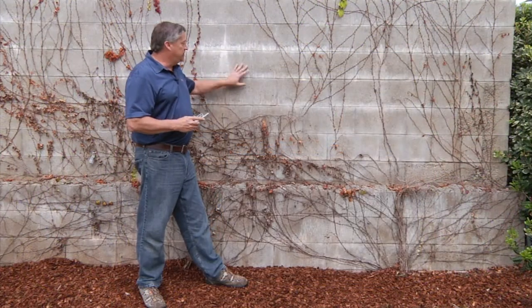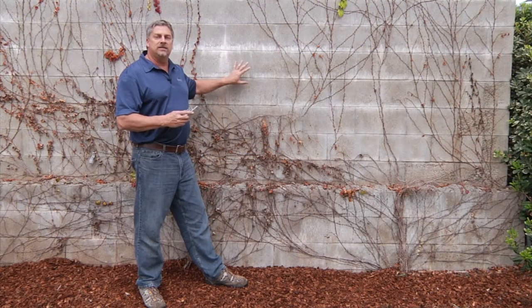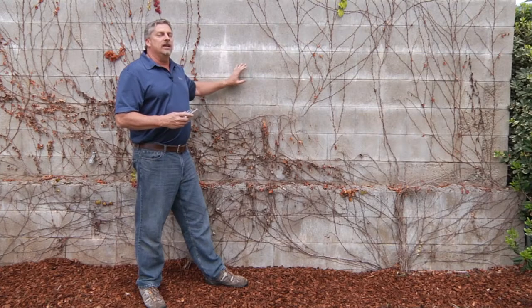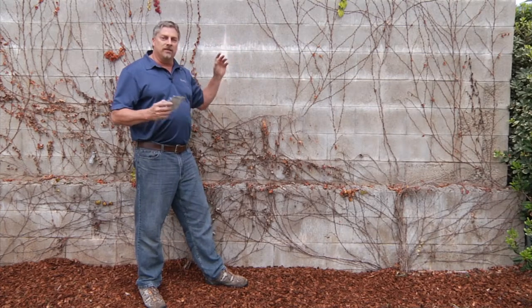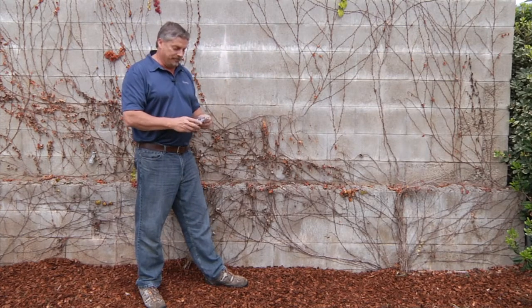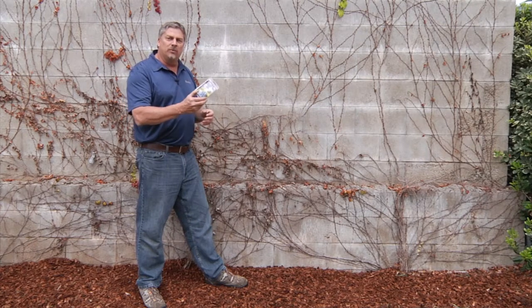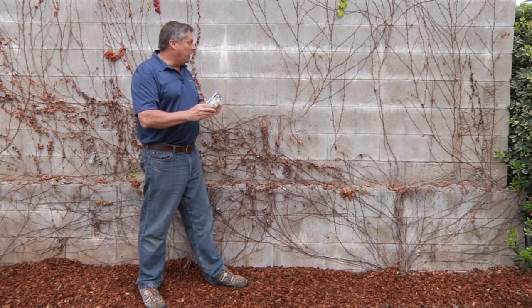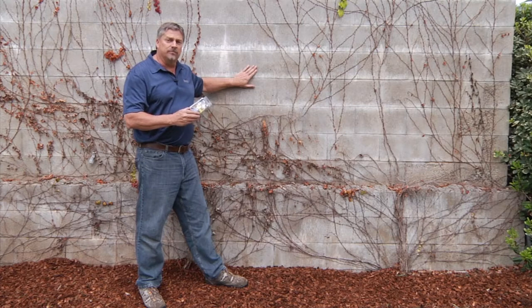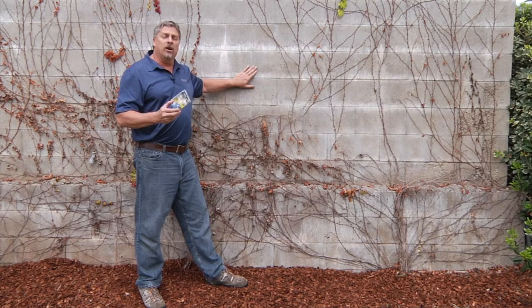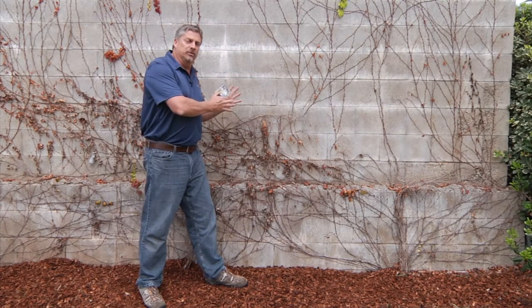So this is a location we've chosen to install our example ACC wall mount controller. It's relatively out of the elements and out of the line of fire from direct sprinkler spray. As well, I've purchased some hardware separately that would work well for this block application. You'll need to decide what type of hardware will work for where you'll be mounting your controller. So mark the desired controller location on the surface that you'll be using. Then we'll drill out the top center screw hole first.